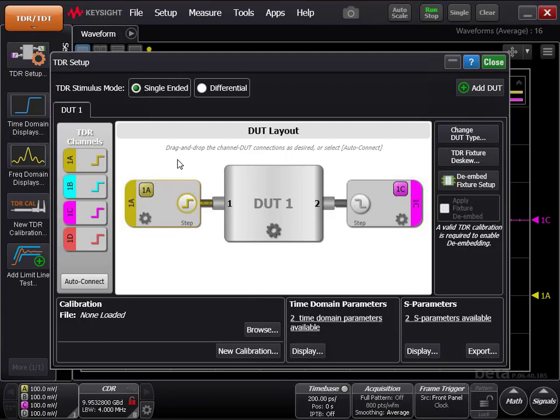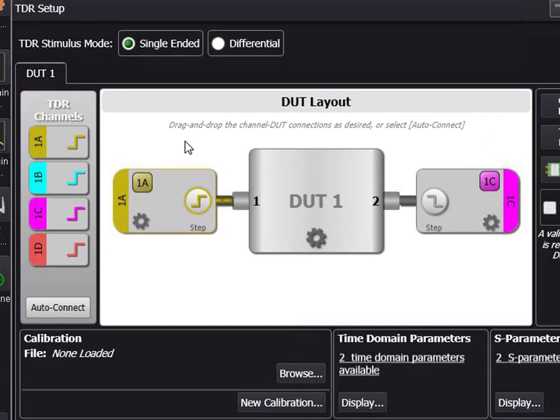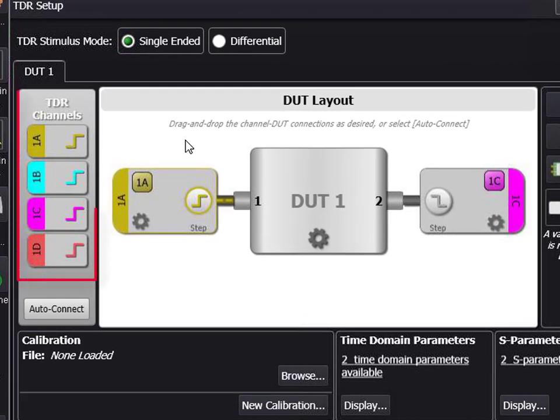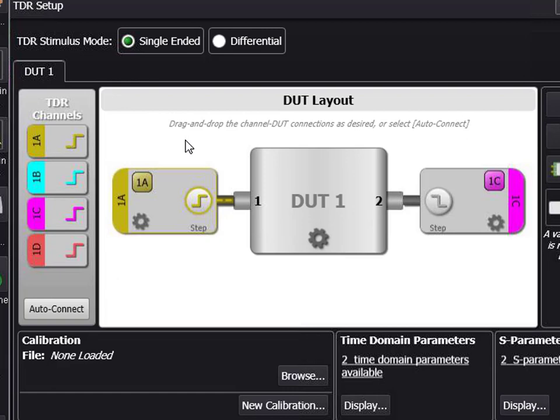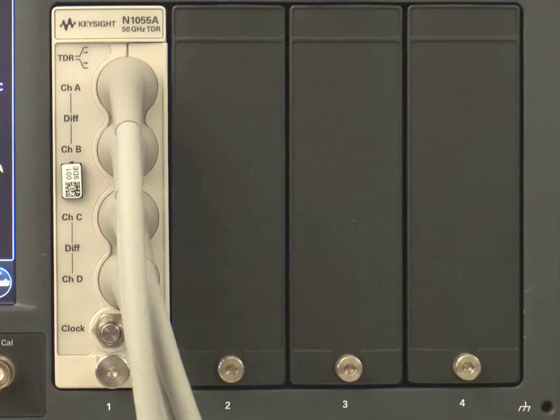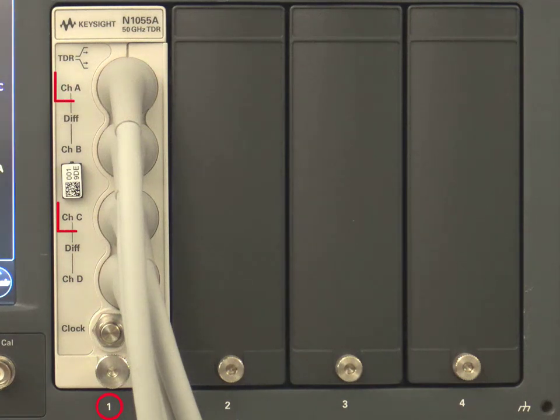If you wish to use different channels, drag them onto the DUT layout from the TDR channels select list. Or, click Auto Connect in the TDR channels list to let the software decide. Please note the names of the channels, 1A and 1C. The number corresponds with which slot the N1055A is plugged into on your mainframe. And the letter corresponds with the measurement head channel.